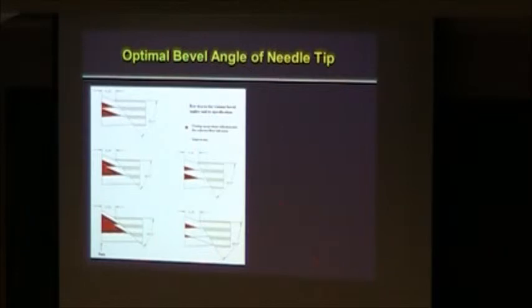The other thing is we also want to maximize placement of this fiber so we can get the fluorescence signal. As I said, it's a weak signal. So they did some ray tracing using the refractive indices for glass and air, and they said the optimum angle is 40. The problem is, if you cut it at 40, for a biopsy, when the needle fires, it has to cut through the tissue. When you have this shallow of an angle, it doesn't cut properly. You need a much deeper angle.